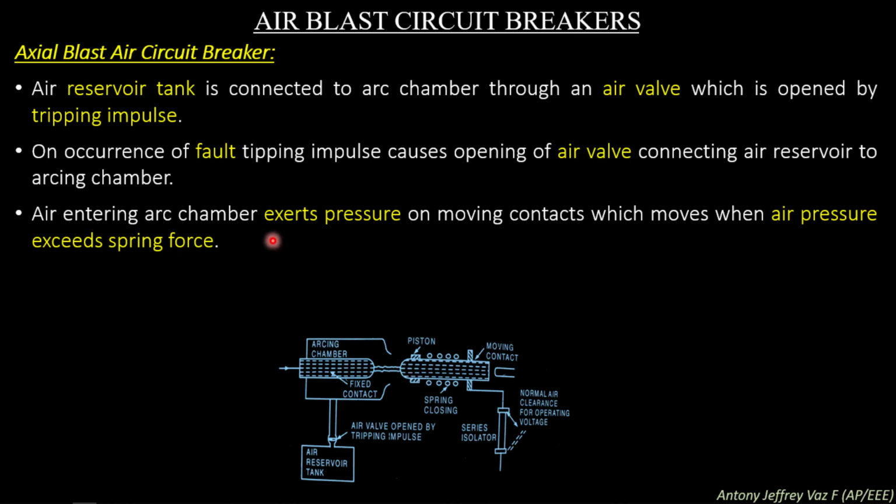Air entering the arc chamber exerts pressure on the moving contacts, which move when the air pressure exceeds the spring force. So, if the valve is opened, at once the pressurized air present in the air reservoir tank will push the moving contacts outside against the spring and move them out, which trips the circuit breaker. The moving contact is separated and at once an arc is struck.